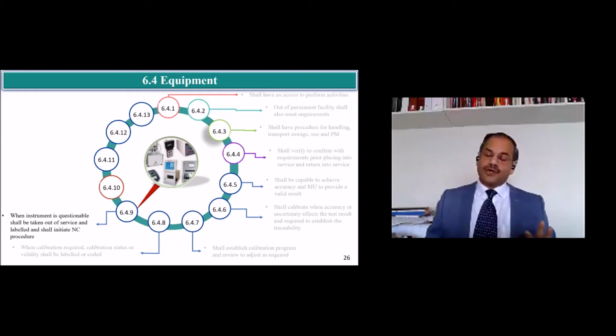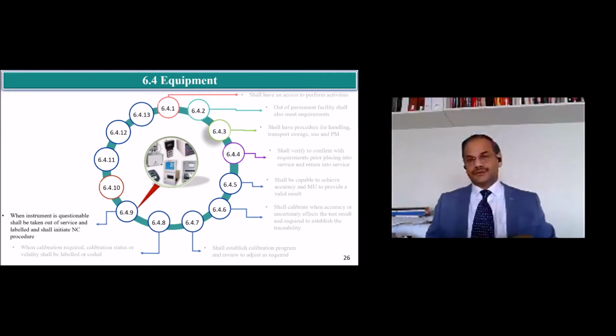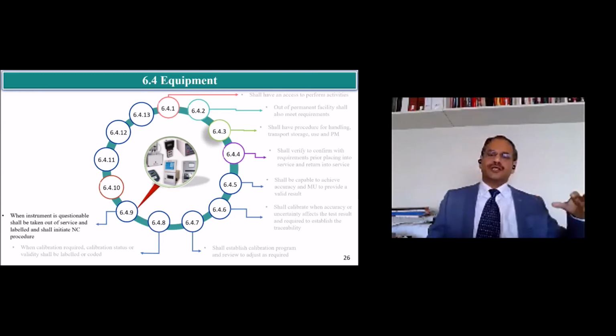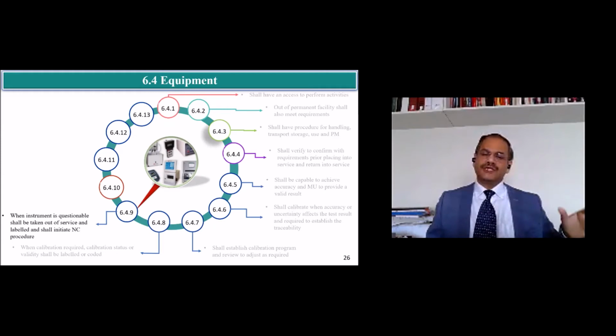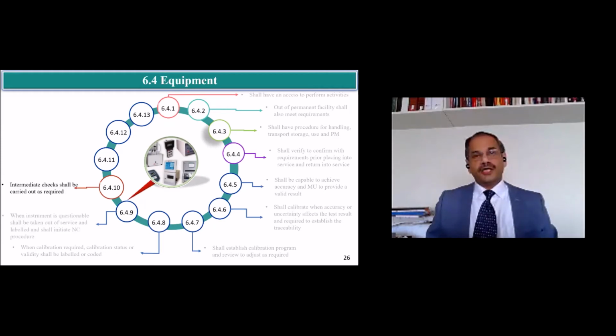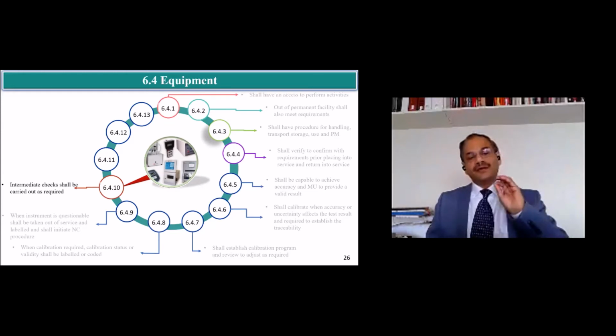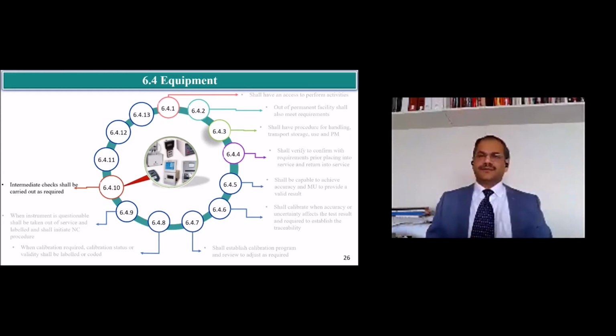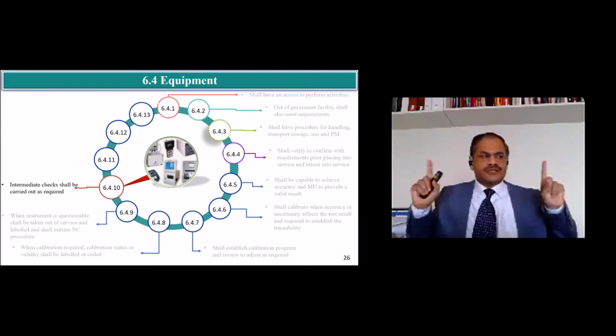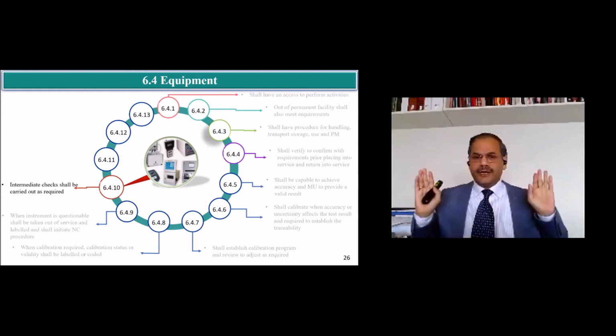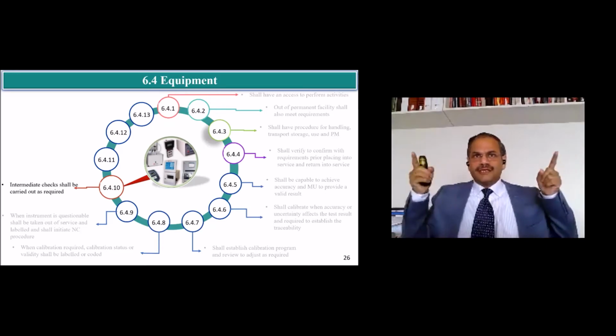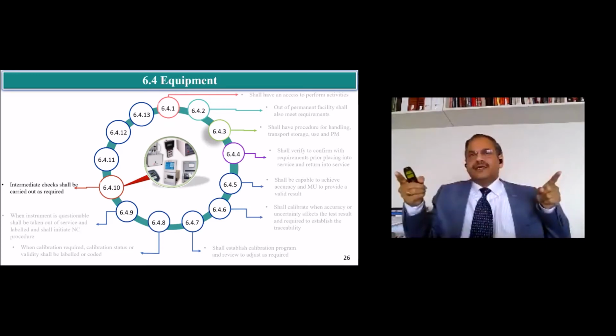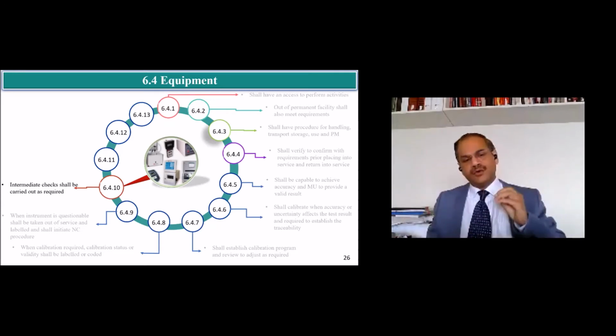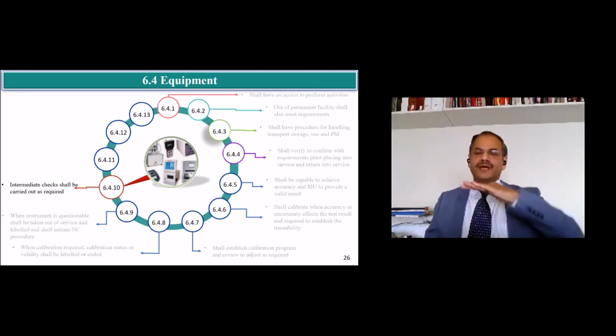When any instrument is out of calibration, it should be taken out of service. You should initiate a non-conformance: why it was out of service, how many results have gone invalid, those types of things. You must investigate all of it. Then all the equipment must have an intermediate check as per your risk assessment, because you may have one equipment whose calibration frequency is once in a year. Perfectly okay. But how would you ensure that this equipment is okay for that whole year?